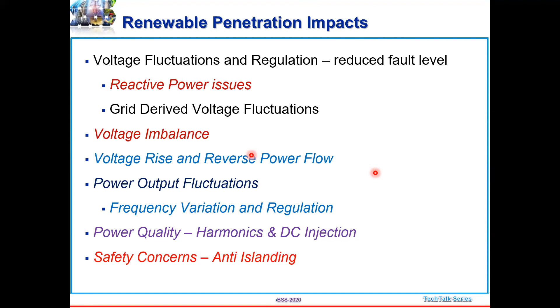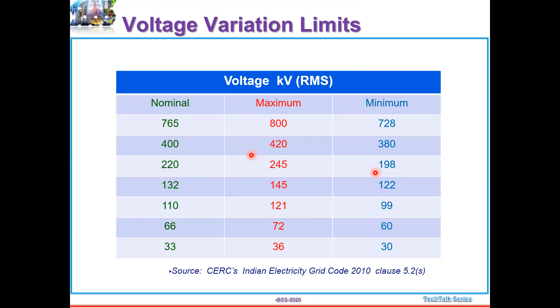And this is the normal voltage level. This is one case which I am going to explain to you. This is the normal voltage level as per the grid code: for 400 kV, it should be between 380 and 420 kV. What happened was, in March 2019, Karnataka faced around 80 to 90% grid penetration. They had huge wind and solar available at that point of time, so they backed down all the conventional generators during the daytime, and only wind and solar was there, which was around 80 to 90% penetration compared to the normal demand.